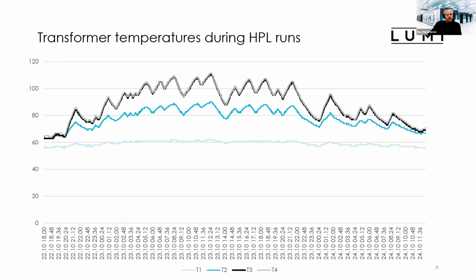So then something about the HPL runs. As Samuli mentioned, running the HPL at the system size of LUMI is not just a single attempt and then get the results out. When you are pushing back-to-back HPL runs on the GPU partition, for example, if a run fails with some node failure or a network error, you need to push a new run and try to get the result out. And what we noticed when running these back-to-back HPL runs is that our transformer temperature started to increase to pretty high levels. So 110 degrees was reached in these two transformers, which are feeding most of the biggest partition of the GPU cabinets. So then we discussed with the vendor that there should be a little bit more cool down between the HPL runs to avoid this kind of issue.